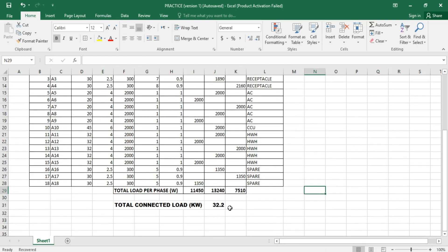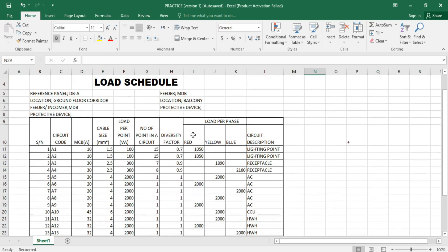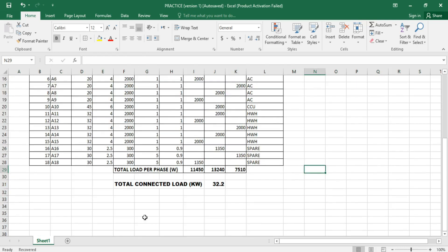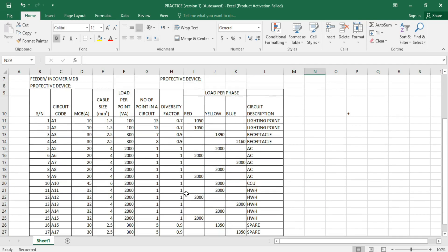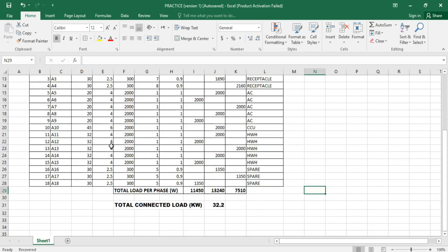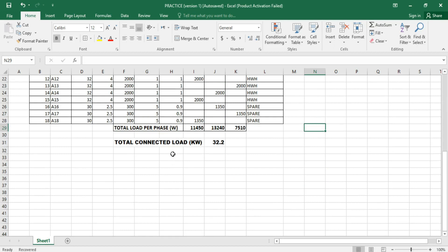So we're having 32.2 kilowatts of load connected to this building. We still need to calculate the amperage so that we can be able to specify our protective device. This can be calculated by using the P = IV power factor formula.